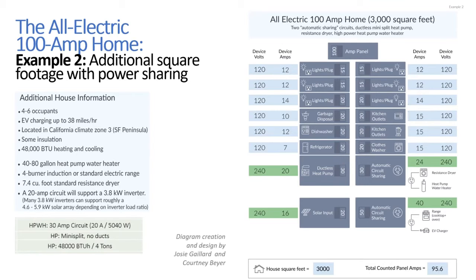On the right side, we had to do circuit sharing. Since we were using automatic circuit sharers that alternate which device is getting power, the second from the bottom has the resistance dryer and a heat pump water heater—while the clothes are drying, the water heater pauses and waits to recharge until the clothes are dry. In the far bottom right, the range and an EV charger take turns. While dinner's cooking, the EV—which was supposed to wait till midnight anyway—just can't get power at the same time as dinner's cooking, and later it can get power. That's an example of really trying to see how far to stretch it. Next.